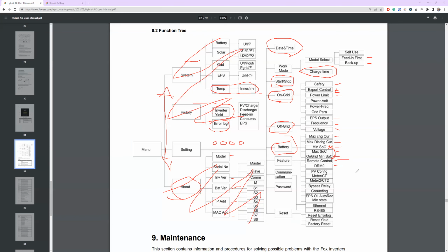So the energy companies are able to tell inverters to stop producing so much solar, or start producing maximum solar, or stop producing solar at all. The various DRM0 modes can be controlled either via a direct connection into the inverter, or by the inverter picking up this sort of remote signal in the AC connection.